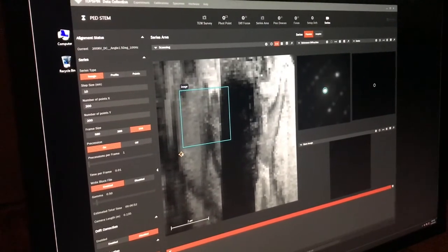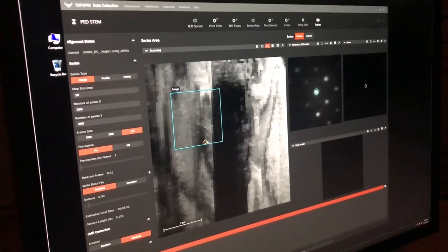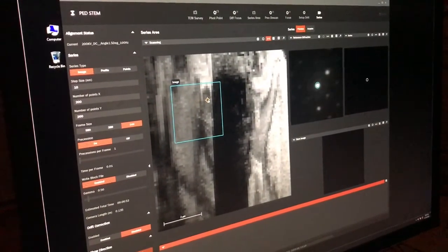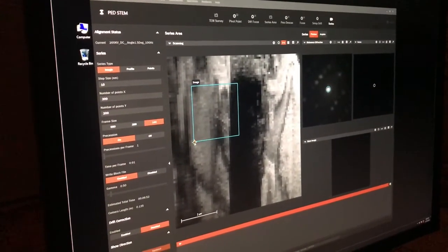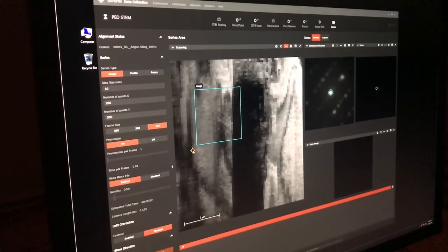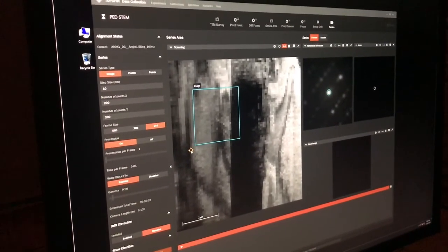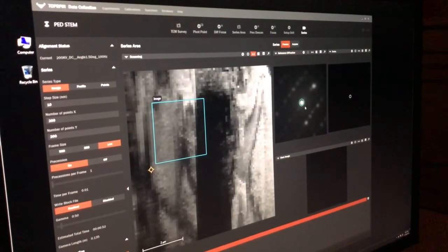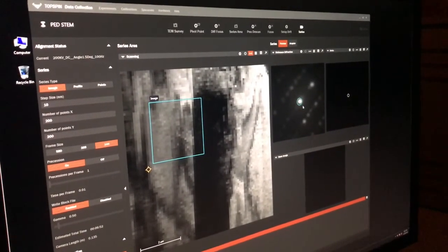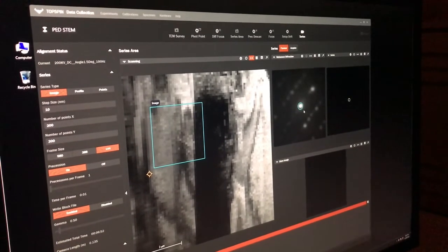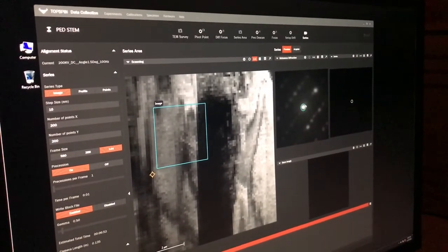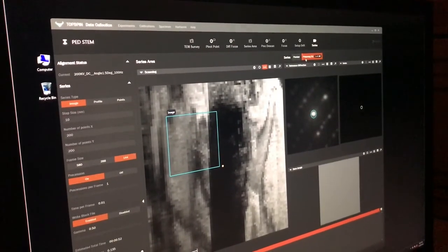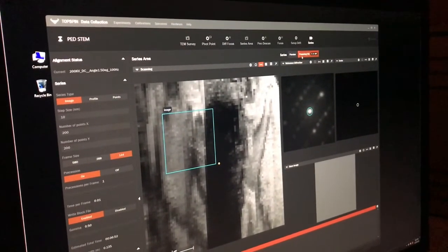After identifying the area of interest, move the cursor around to make sure the diffraction pattern looks nice. Place the cursor to the bottom left of the box because the scan starts from the bottom left. Double check a few more things. Make sure the diffraction spots are centered and the transmitted beam is within the blue circle. Click on acquire. The acquisition has started.